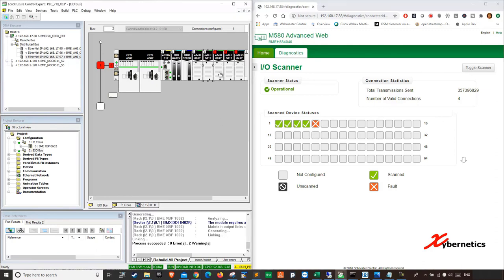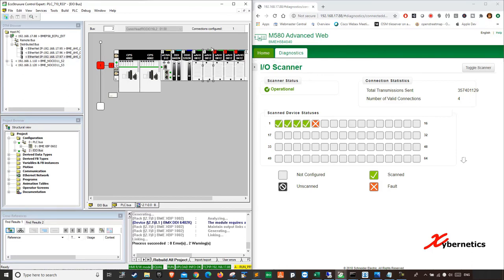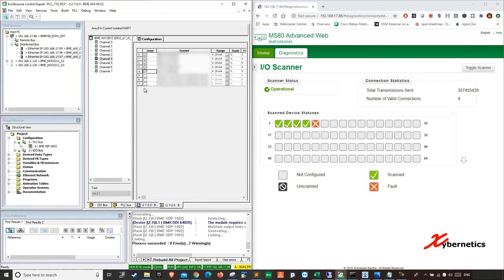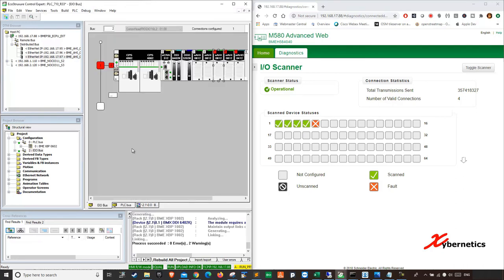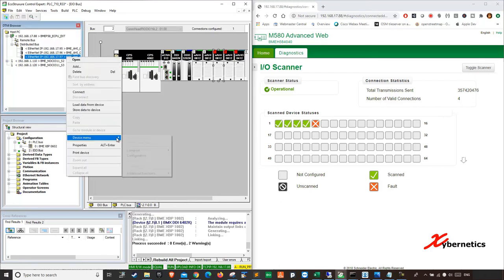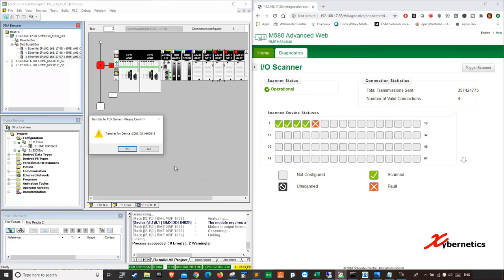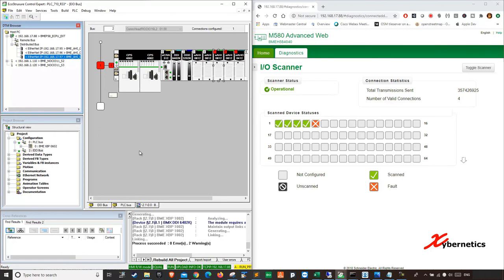What's causing an error is that right now this panel is not hooked up to anything at all. It's expecting 4 to 20 milliamps, but it's not hooked up to anything at all. So if you want to see this turn white, how you do it is you double click this, double click the card itself. It brings you to a section where they allow you to select the channel number. If you click any of this, it's actually the channel number. So what you have to do is you have to click this and remove all this one by one. So you close this, say yes, and hit yes.